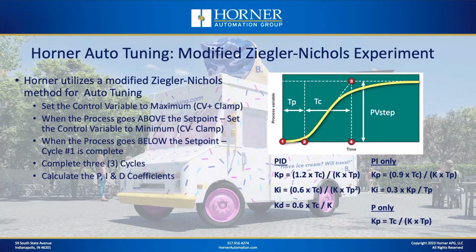Okay, now let's get back to that auto-tuning I talked about. First of all, auto-tuning is not the panacea for every application. As a matter of fact, there are plenty of applications where auto-tuning just doesn't work very well, and you'll need to use a manual approach, either to get a better tune, or maybe a faster tune, or maybe just so it's possible at all.